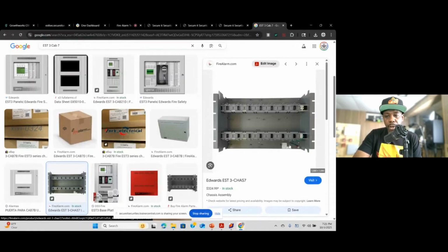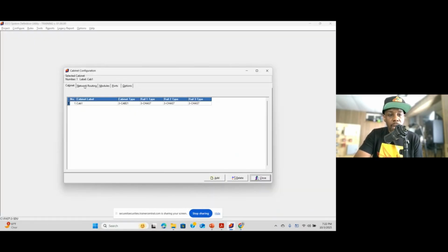And when you have your whole system set up, they have 2 different layers, right? They have a hardware layer, which consists of the actual cards, and then they have the software layer, which will consist of the actual buttons and switches. And I'm going to show you what that looks like. So we have an idea of what type of system we have because we just have a small system: CPU, power supply, and a loop controller. So inside here, we're going to add a cabinet.